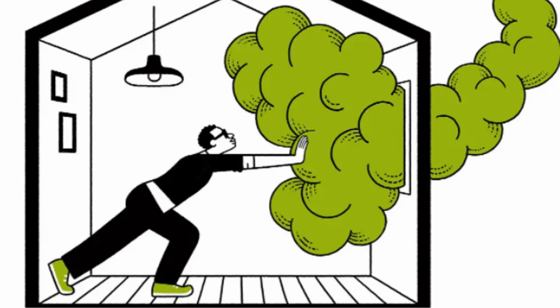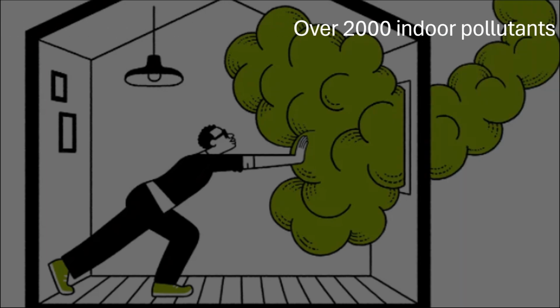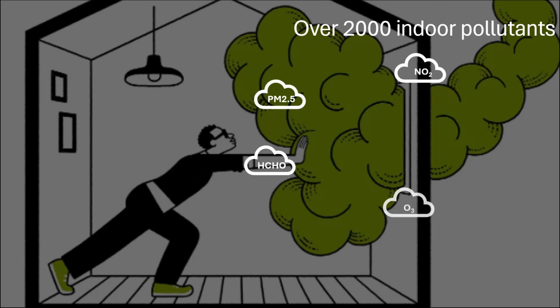There are literally thousands of different types of indoor air pollutants. Leaving out infectious pathogens, about 5 pollutants are considered to be of primary concern. There's formaldehyde from building fabric, particulate matter, specifically PM 2.5, ozone, nitrogen dioxide, and these can have outdoor sources. Nitrogen dioxide and PM 2.5 can also be generated due to occupant activity indoors, like cooking, burning candles. Radon enters buildings from the ground.